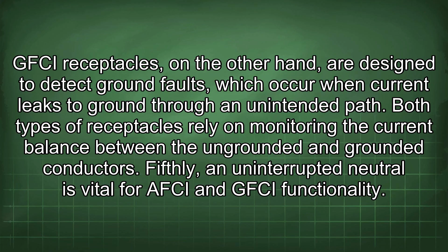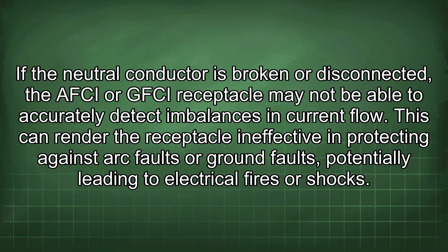Fifthly, an uninterrupted neutral is vital for AFCI and GFCI functionality. If the neutral conductor is broken or disconnected, the AFCI or GFCI receptacle may not be able to accurately detect imbalances in current flow. This can render the receptacle ineffective in protecting against arc faults or ground faults, potentially leading to electrical fires or shocks. Therefore, it is absolutely essential to ensure that the neutral conductor is continuous and properly connected throughout the entire multi-wire circuit.